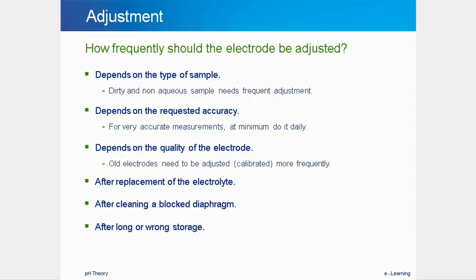For standard use with easy samples, the electrode should be adjusted at least every day before measurements are begun. With more demanding samples which are dirty or non-aqueous, adjustment needs to be performed more frequently. If high accuracy is required, adjustment should be performed more often. With older electrodes, adjustment also needs to be performed more frequently. After certain procedures the electrode always needs readjustment — these include replacement of the electrolyte, cleaning of a blocked diaphragm, after storage, and after regeneration.